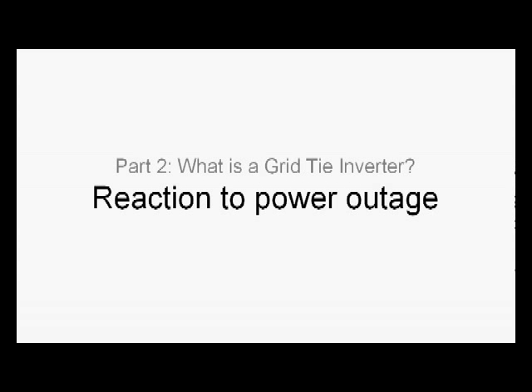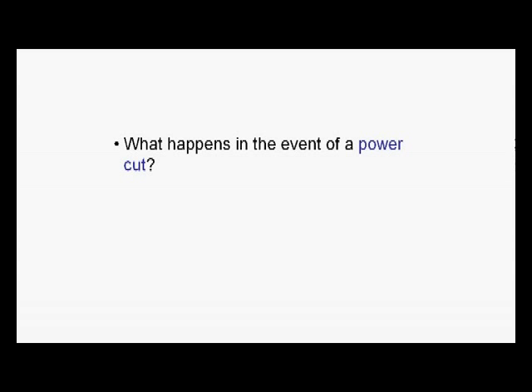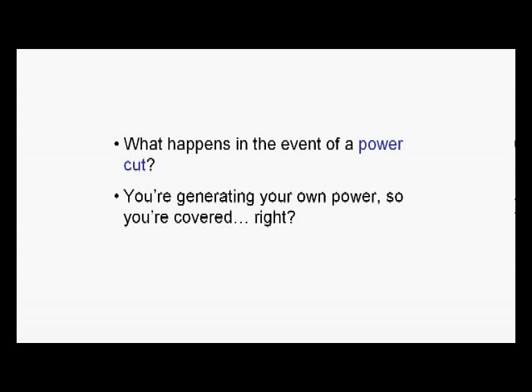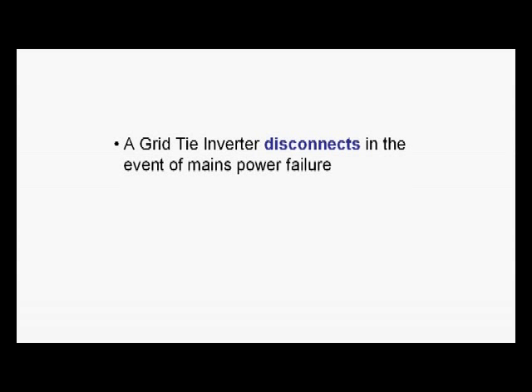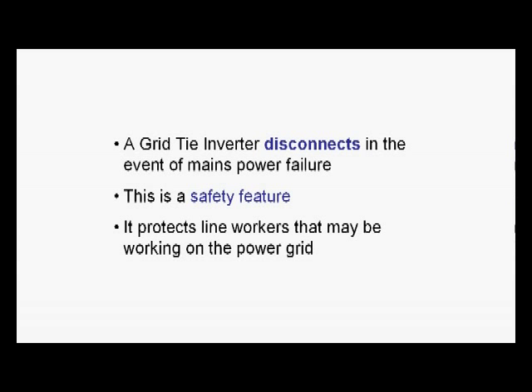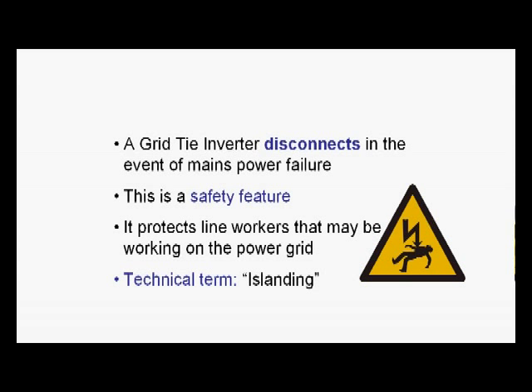Let's talk about the reaction to a power outage — what happens in the event of a power cut. You might think that since you're generating your own power from your solar panel or wind turbine, you're covered. Wrong. A grid tie inverter actually disconnects in the event of a mains power failure, so even if the sun is shining on your solar panels or the wind is blowing on your wind turbines, your grid tie inverter will not produce an output if it doesn't detect mains power. This is a safety feature that protects line workers who might be working on the power grid — the technical term for it is islanding. Your power company will be more than keen to ensure that any grid tie device you use has this feature.